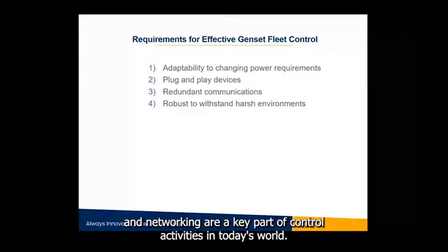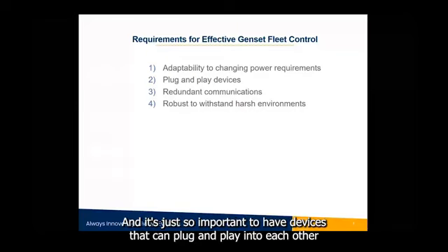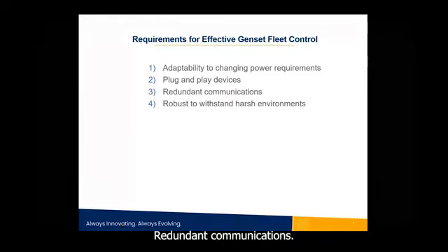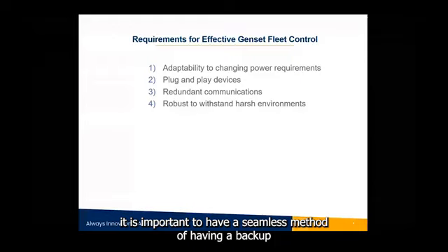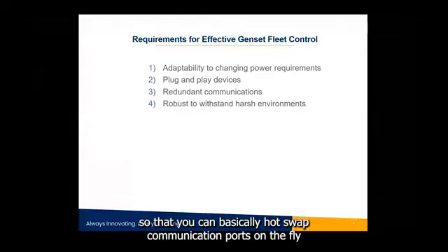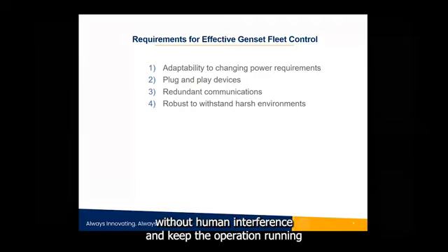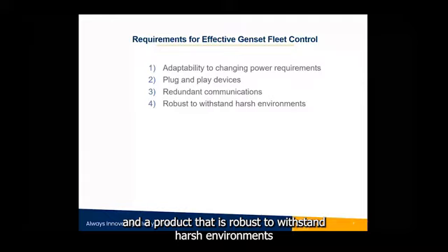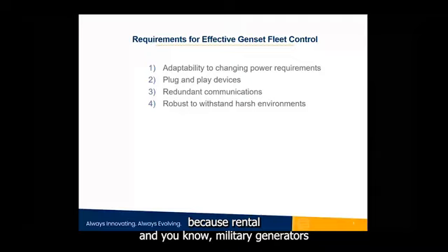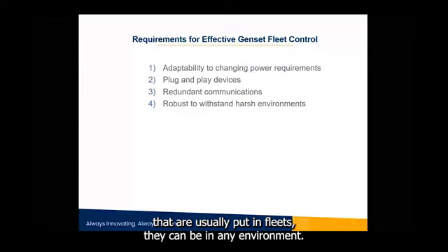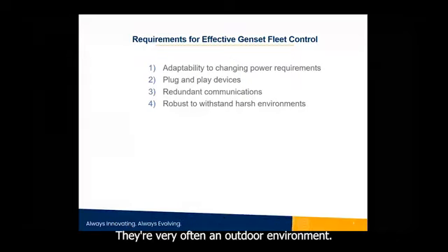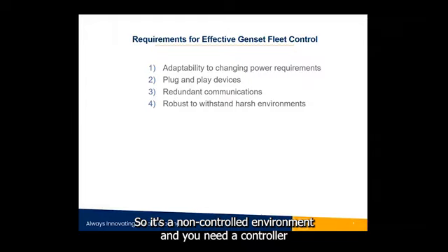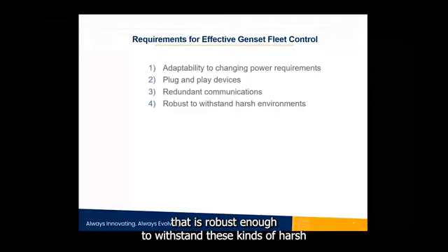Communications and networking are a key part of control activities in today's world. And it's just so important to have devices that can plug and play into each other as well as into other devices. Redundant communications. Well, if you have a communications failure, it is important to have a seamless method of having a backup so that you can hot swap communication ports on the fly without human interference and keep the operation running. And a product that is robust enough to withstand harsh environments, because rental and military generators that are usually put in fleets can be in any environment. They're very often in outdoor environments, so it's a non-controlled environment, and you need a controller that is robust enough to withstand these kinds of harsh environments.